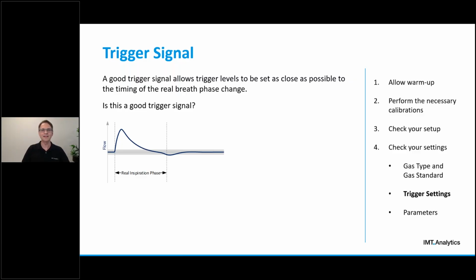So let's see if that's a good trigger signal. It actually turns out that it's not, and here is why. The first part actually looks great. As the flow signal is rising rapidly here, we talk about a steep slope of the waveform. We can nicely set a start trigger quite close to the area we want to avoid on a rising edge of the signal, and sufficiently capture the start of the inspiration phase with our analyzer.